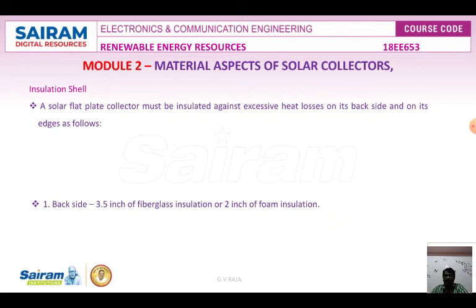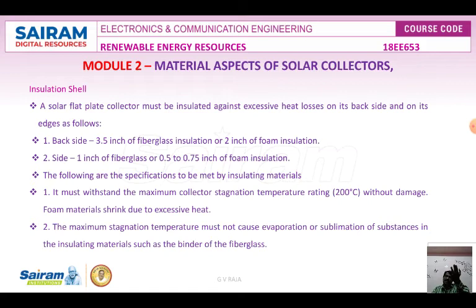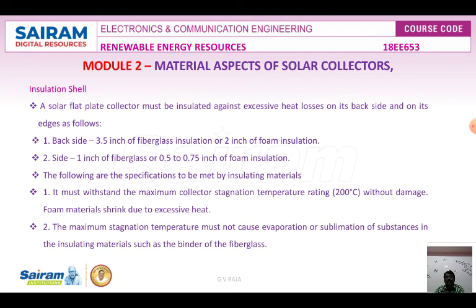The insulation shell is at the bottom of the collector. The top is the absorber, the middle is the glazing material, and the bottom is the insulation to avoid heat loss. For solar flat plate collectors, insulation is applied on the back side and edges — 3.5 inches of fiberglass insulation or 2 inches of foam insulation on the back, and 1 inch fiberglass or 0.5 to 0.75 inches of foam insulation on the sides.